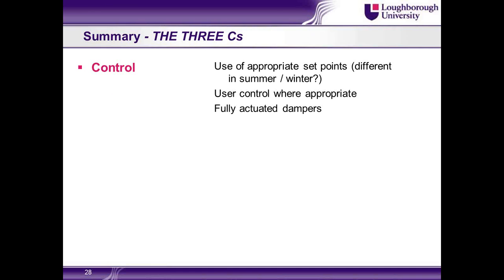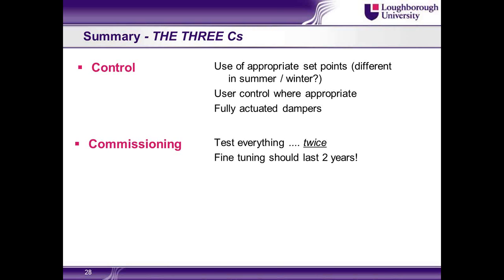control. No point in designing a naturally ventilated building if it's not controlled appropriately. So that means appropriate set points, which may be different depending on the season. Offering user control where appropriate, fully actuated dampers. Second one is commissioning. Test everything, test it twice, make sure that it's doing exactly what it should be doing. And then there really should be some fine-tuning that goes on for at least through two seasons.